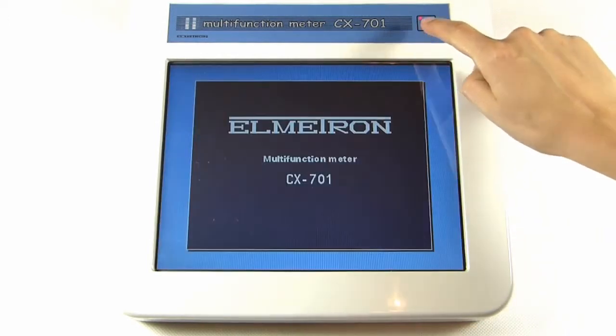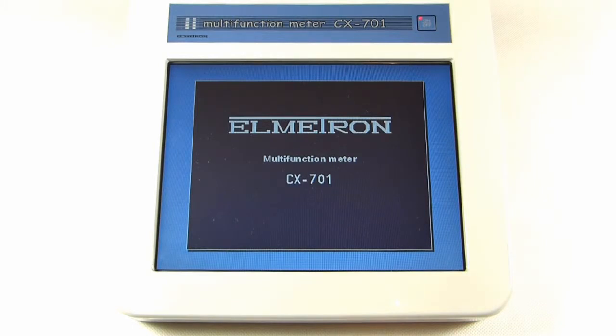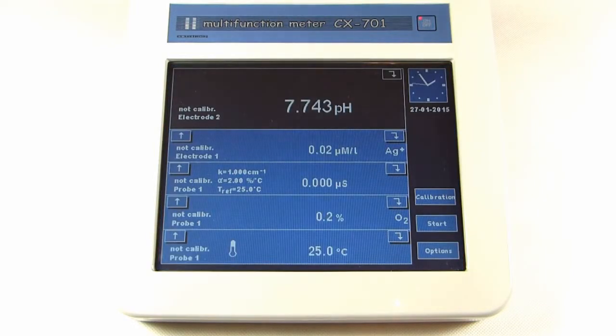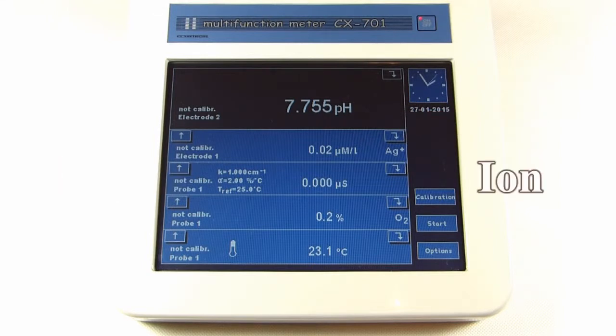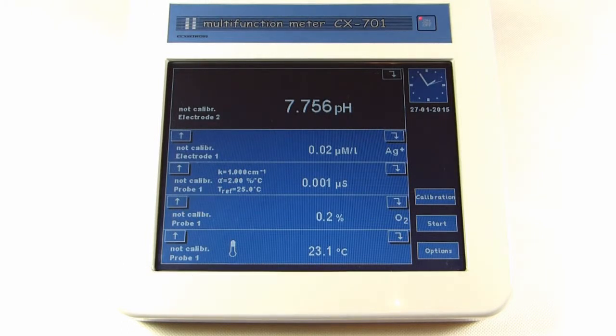The meter is switched on by pressing the on-off button. Measuring mode. CX-701 is an accurate, multifunction modern device used to measure basic physical and chemical parameters of water, sewage and chemical compounds. It measures pH, redox potential, conductivity, salinity, concentration of oxygen in water or air, ion selective measurements, temperature and atmospheric pressure. It also enables semi-automatic titration.